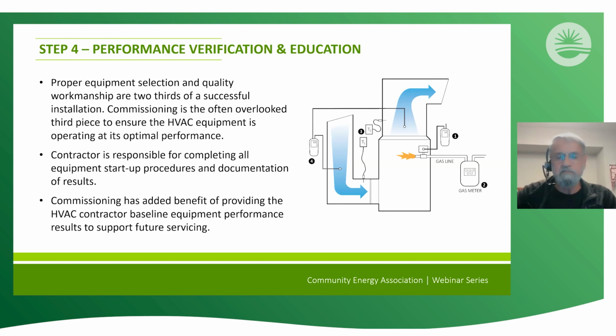And what that is, it's not just a shakedown. You just install a new system. Maybe there's a part or a component from the manufacturer or the supplier that's not working. You want to find that now, not down the road late on a Sunday night in the middle of winter when the homeowner calls you. You want to do the whole shakedown now. So that's part of it. The other thing is you've got a complex system, and the manufacturers engineered the system, manufactured and shipped it with some expectations of you checking: make sure the refrigerant charge is this much, making sure the gas pressure is between here and here, and the temperature rise, the difference between the temperature coming back from all your registers to the equipment and the temperature leaving. What's that temperature rise? Makes a big difference.